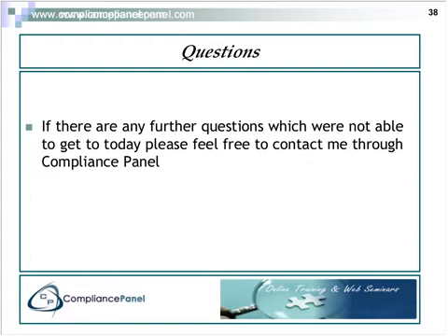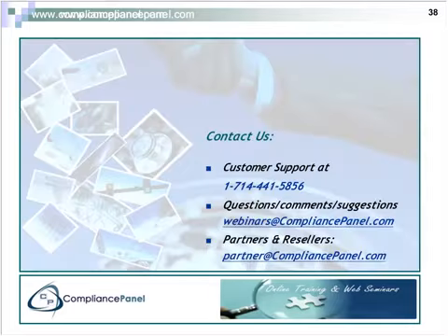Is it required to conduct supplier audits? It's not required to do all supplier audits, but I would identify those components which are critical to your device and make sure that those suppliers are audited. It doesn't mean you have to physically go to their facility, but you can send them a survey to see, hey, are you guys ISO 13485 certified, or when's the last time the FDA visited your facility?